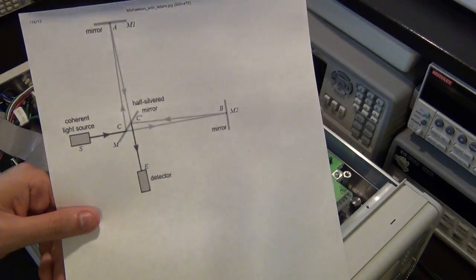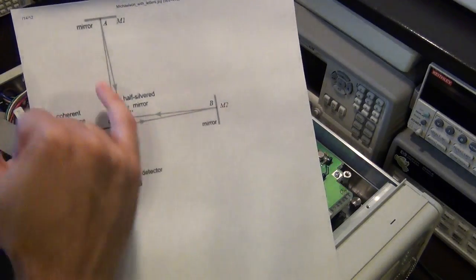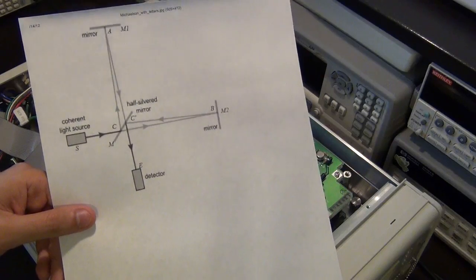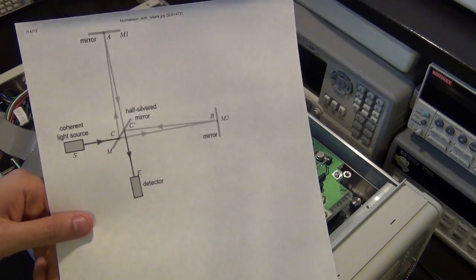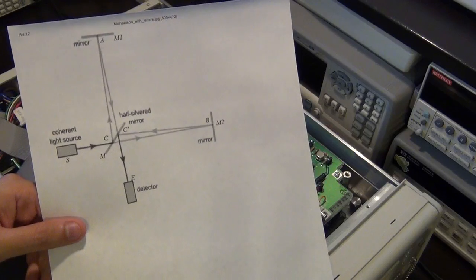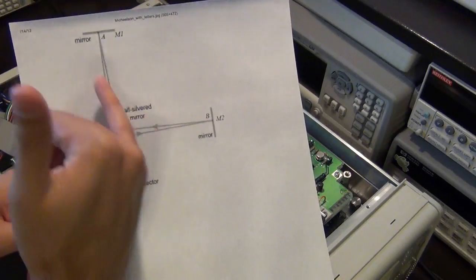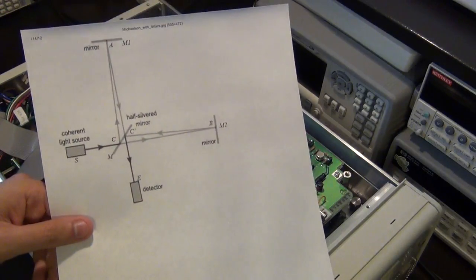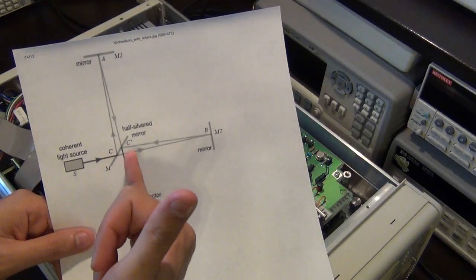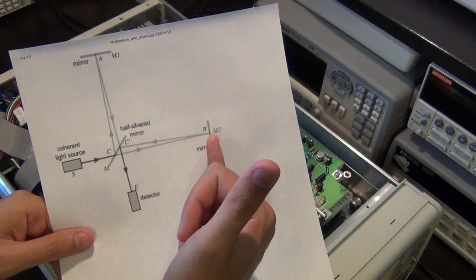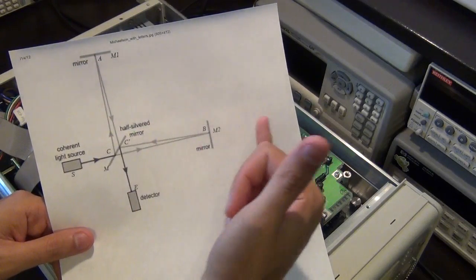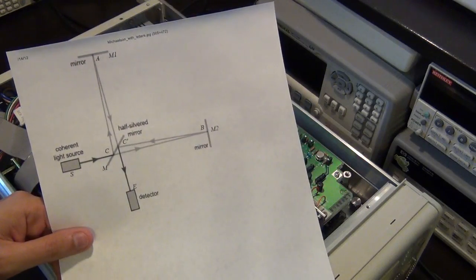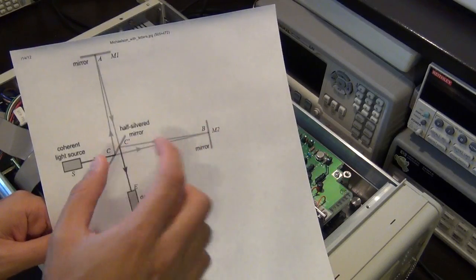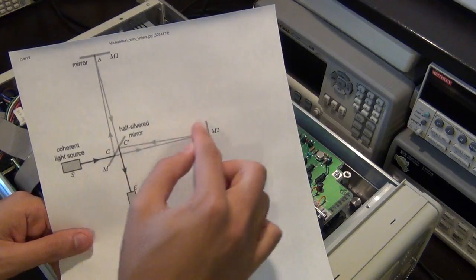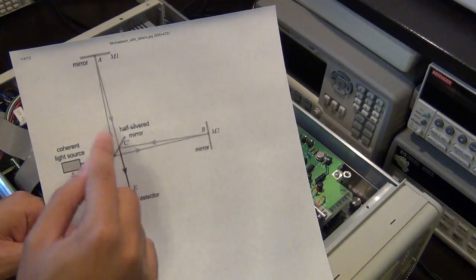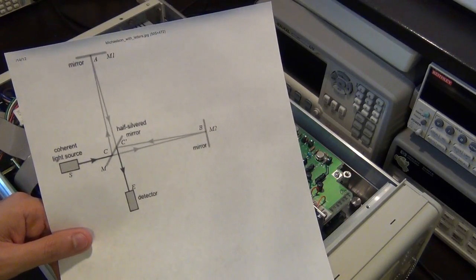But because this is a coherent light source and monochromatic, these two, when they combine on the detector, create fringing patterns due to destructive and constructive interference of light, because the wavelength, depending on the distance in here, creates a different type of fringing. So you can imagine if I change the distance between one of these mirrors with respect to the other mirror, I can change the fringing pattern, because it's the distance or the time that it takes for the light to go back this way and this way with respect to each other that defines the fringing pattern.